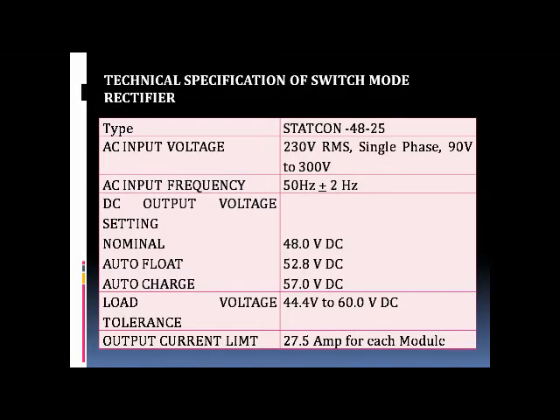Technical specification of switch mode rectifier. Type STATCON 48-25. AC input voltage 230 volts RMS, single phase, 90 volts to 300 volts. DC output voltage settings: nominal 48 volts DC, auto float 52.8 volts DC, auto charge 57 volts DC.